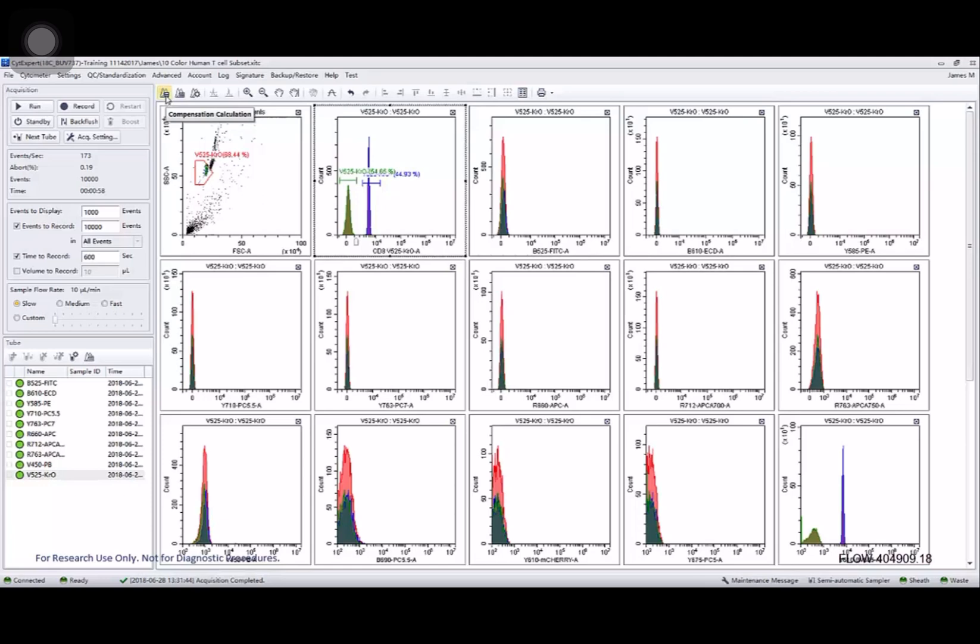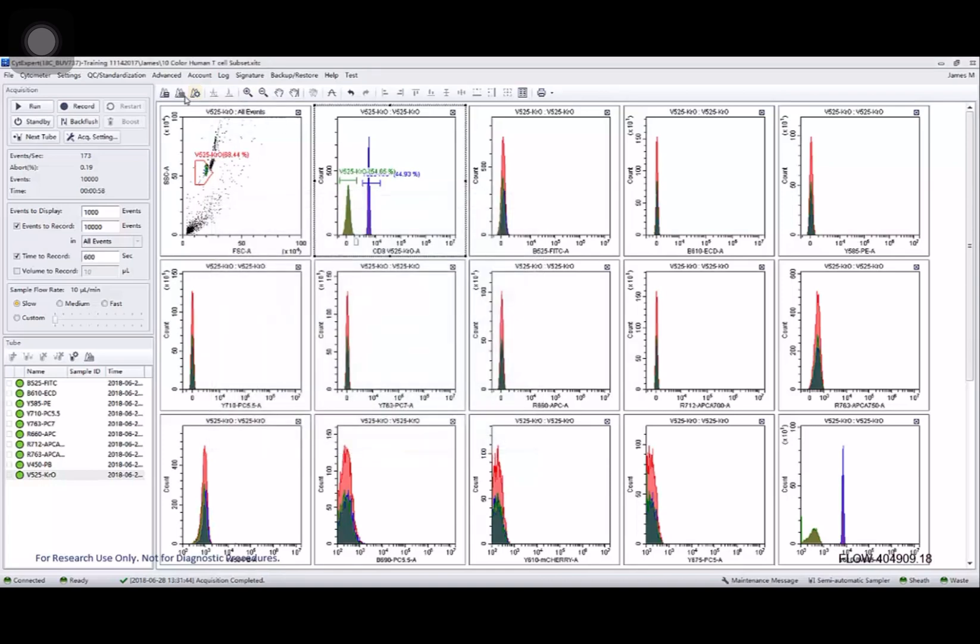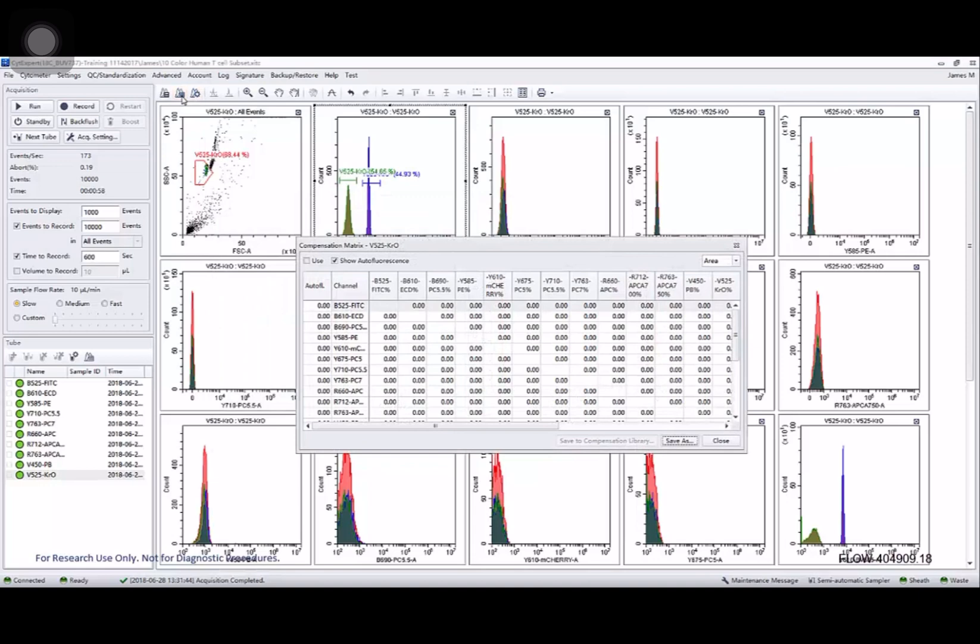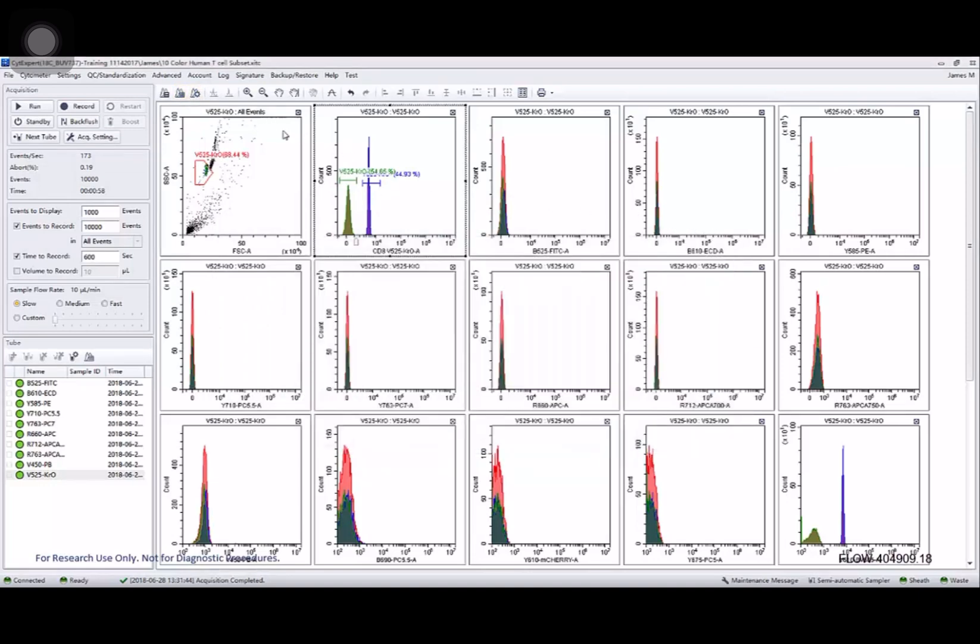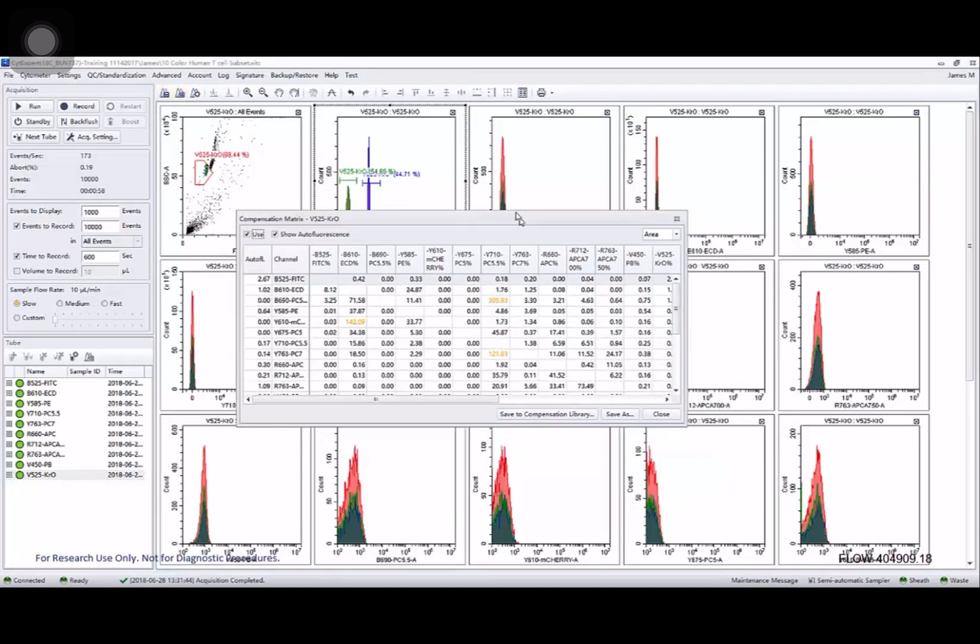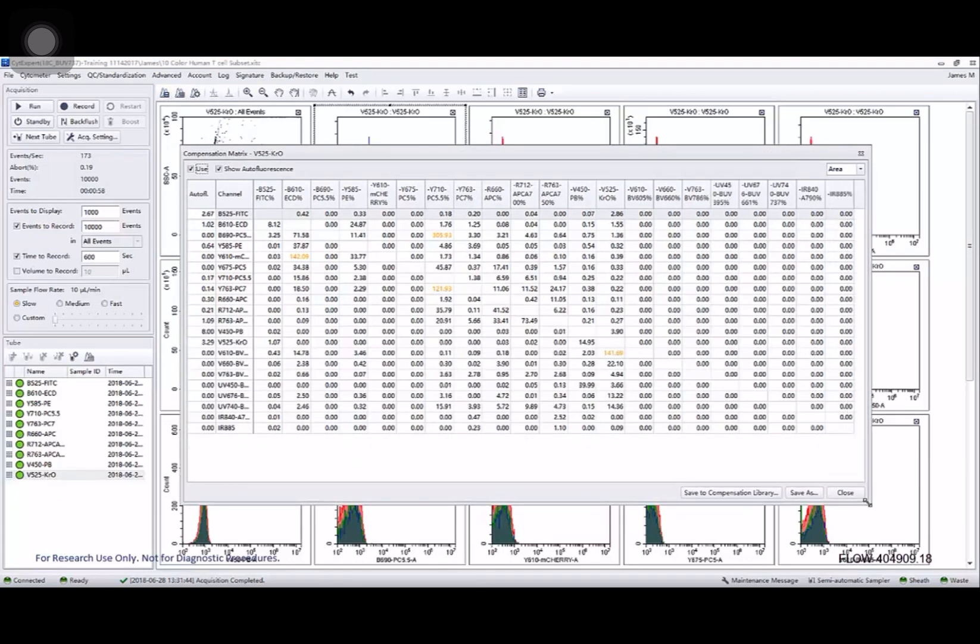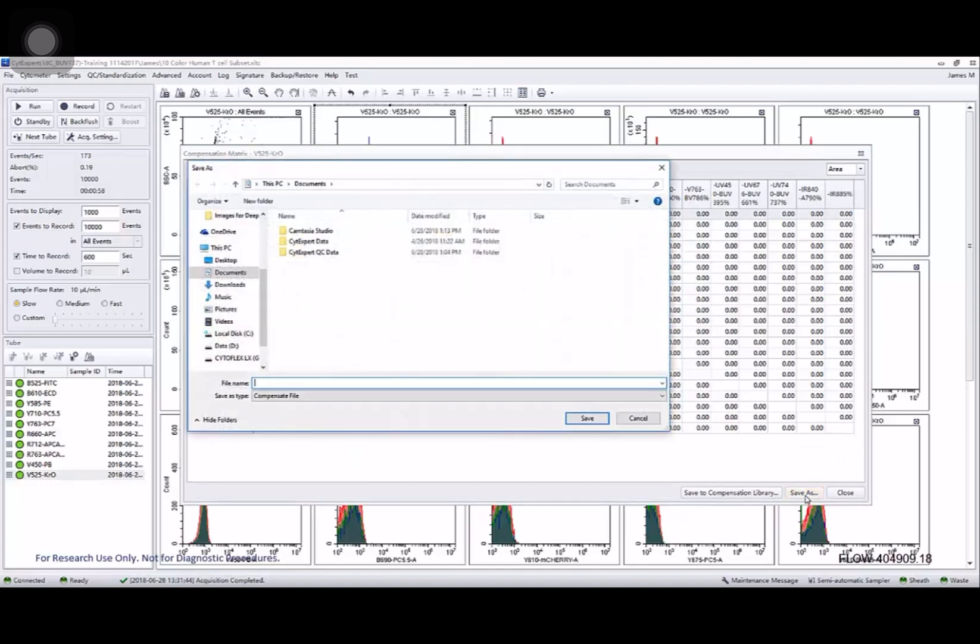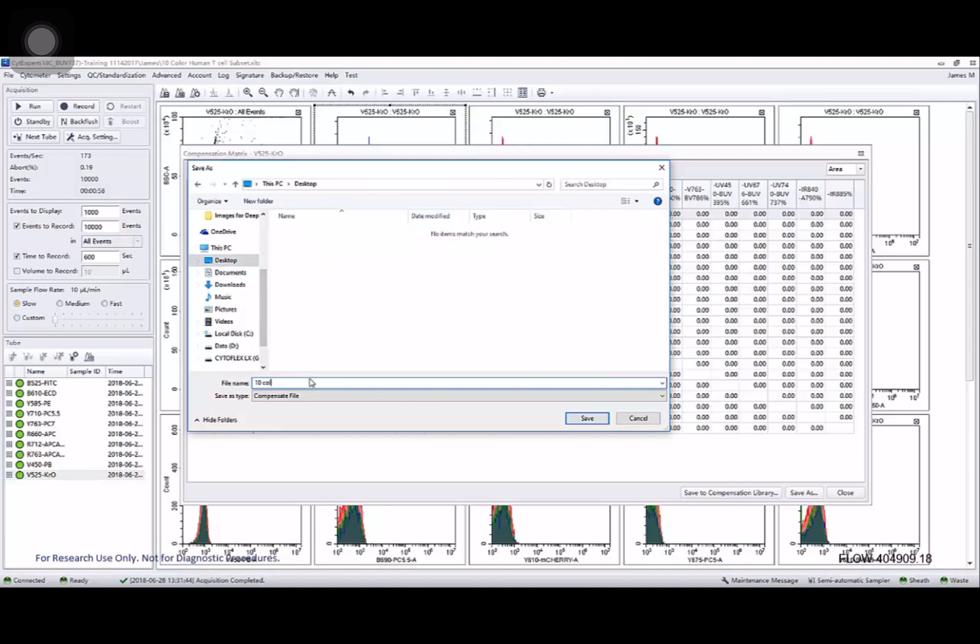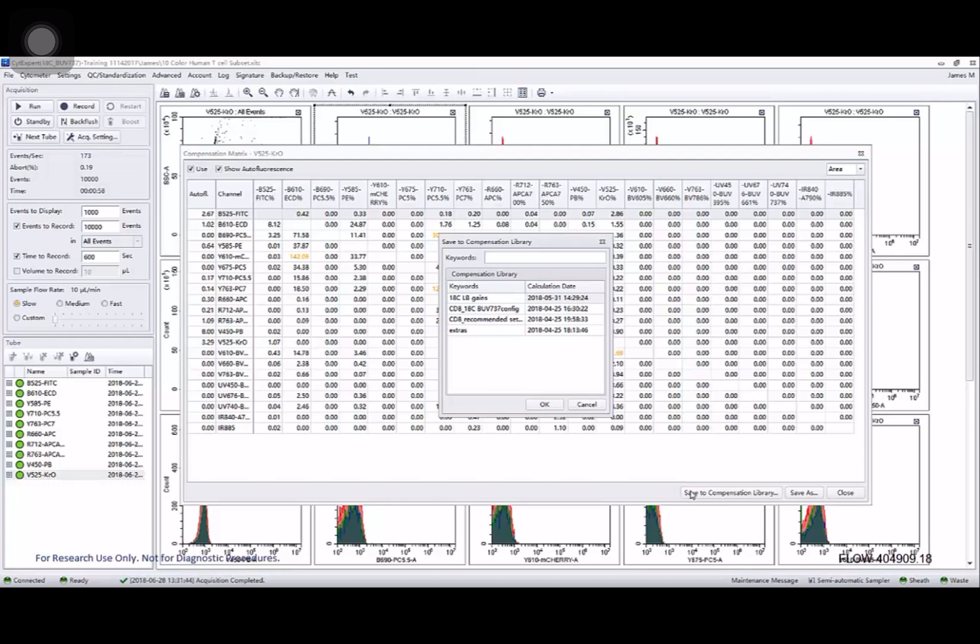Now I've run all those. Let's see what we can do. If I click on compensation setup I can go in here and change anything that I've already created. If I go to matrix that's currently all zeros. And if I go to compensation calculation my matrix is calculated and presented to me. Once I have this I can save it as a .comp file for loading in later. Or I can save it to the compensation library to load into later to new experiments. So I'm going to save that to the library.